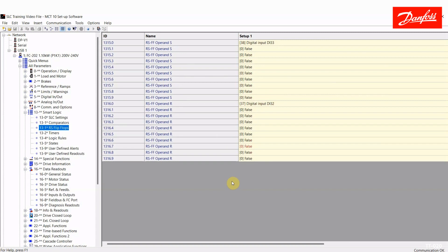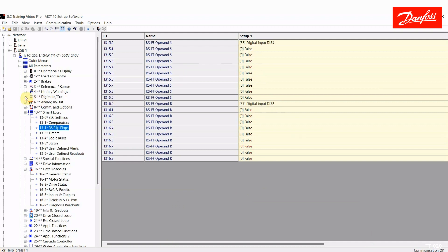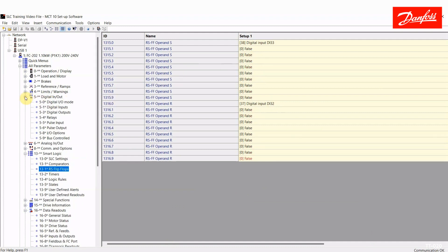Now let's move to flip flops. This is a set reset type flip flop which means a certain event will set the flip flop and a certain event will reset it. When the flip flop is set, you ultimately end up with a digital 1 for the status of that flip flop and you can also attach a physical output to RS flip flop 0 through 9. So there are 10 of these also. So I've created a flip flop that is set when digital input 33 is on and reset when digital input 32 is on.